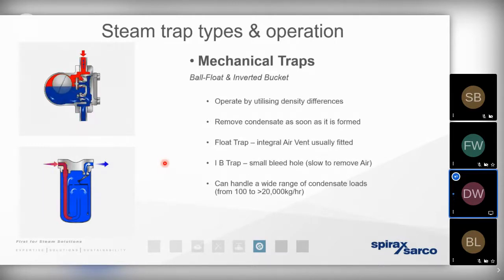Condensate as a liquid is heavier than steam as a gas. And therefore, we've got the buoyancy of either a float or a bucket that will operate, manipulate, a little valve that will allow the condensate to leave the network or the process, but it will lock that valuable steam in.